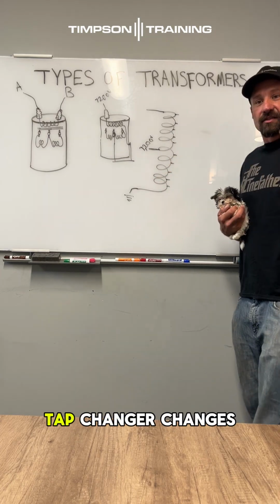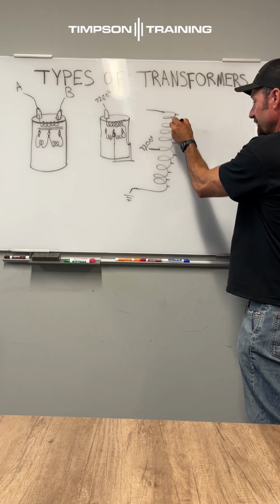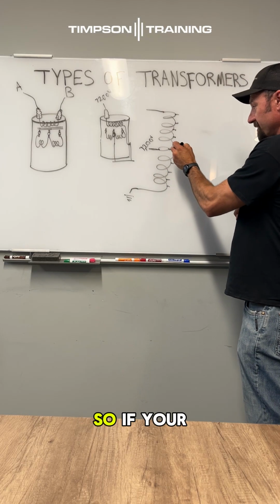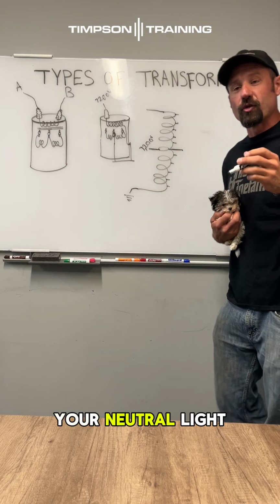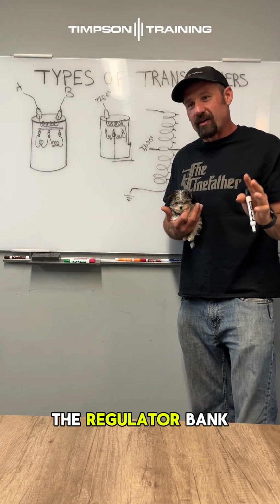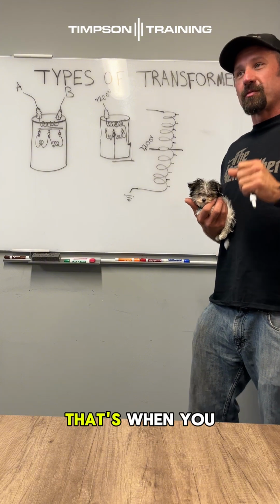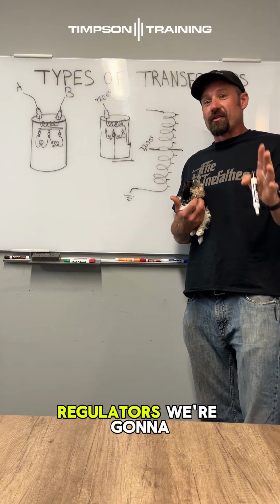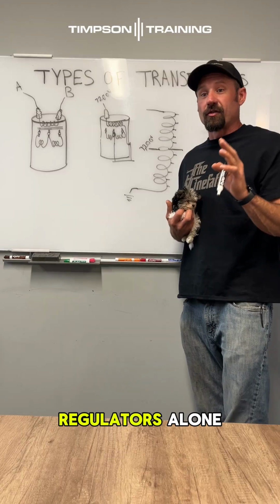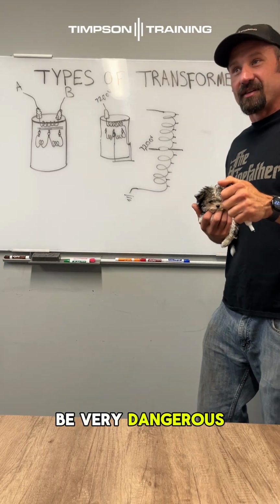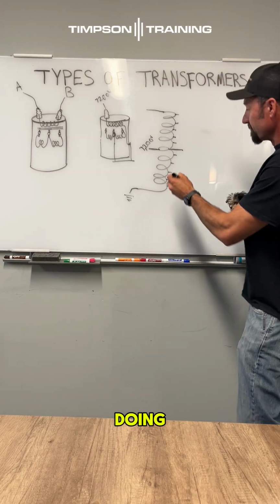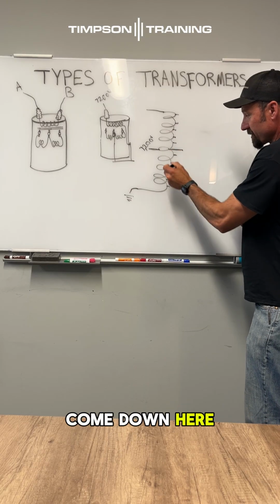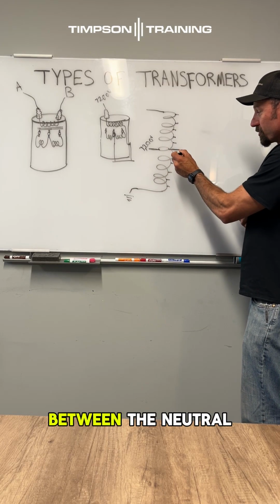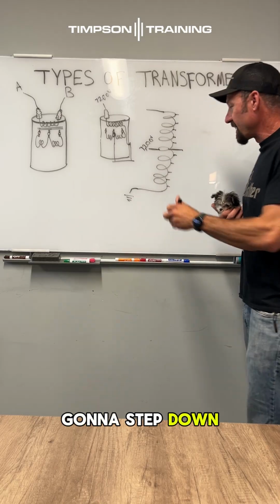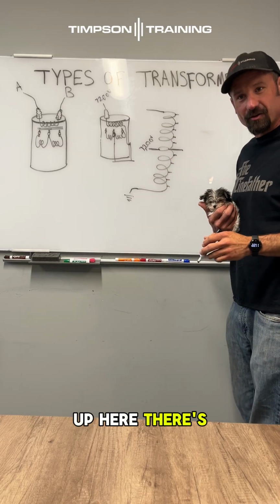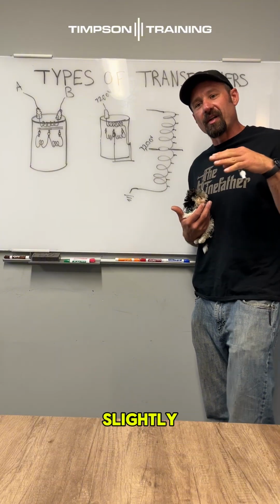And as that tap changer changes, it's moving from here, and this is neutral. So if your tap changer was right here, your neutral light would be on, the regulator bank would be in neutral. That's when you could bypass it. Regulators, we're going to do a whole other video on regulators alone because they can be very dangerous and tricky if you don't know what you're doing. So if you come down here, there's less coil between the neutral and here, your voltage is going to step down. If you come up here, there's more coils, your voltage is going to step up slightly.